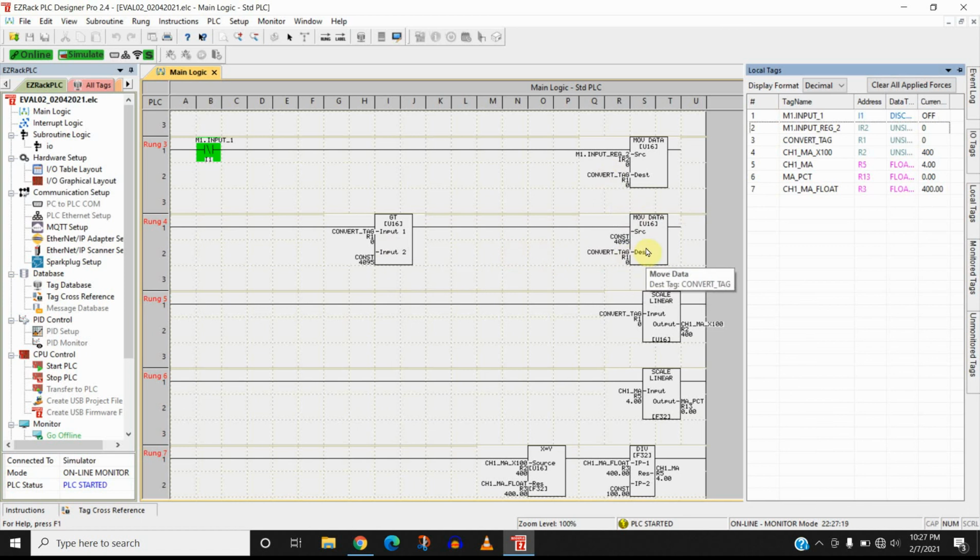So sometimes what you need to do is find out what could go wrong in your program, and then find ways to protect the program from that, by checking the range of input values. Sometimes you can limit the range. If you've got an HMI touchscreen interface, you can probably set the min-max values on the numbers coming into it. But anyway, long story short, the answer to activity 2 is this block right here. The 4 to 20, 0 to 100.